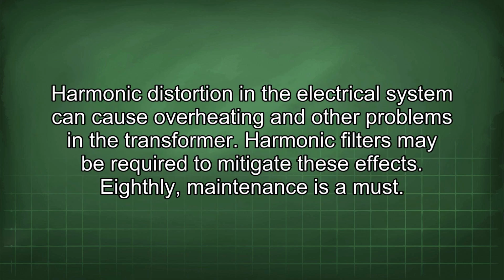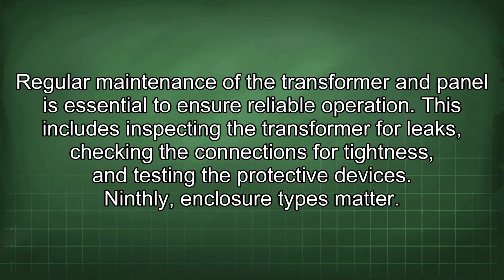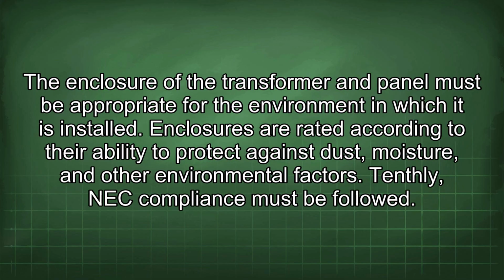Harmonic distortion in the electrical system can cause overheating and other problems in the transformer. Harmonic filters may be required to mitigate these effects. Eighthly, maintenance is a must. Regular maintenance of the transformer and panel is essential to ensure reliable operation. This includes inspecting the transformer for leaks, checking the connections for tightness, and testing the protective devices. Ninthly, enclosure types matter. The enclosure of the transformer and panel must be appropriate for the environment in which it is installed. Enclosures are rated according to their ability to protect against dust, moisture, and other environmental factors.